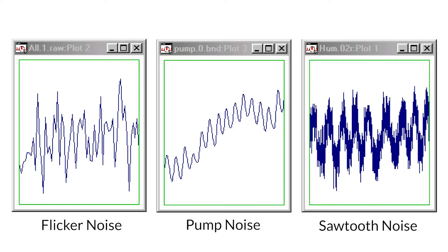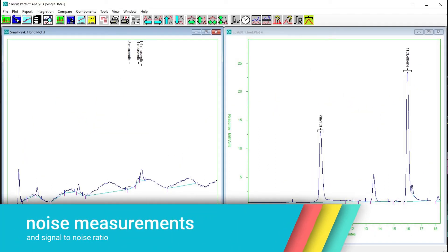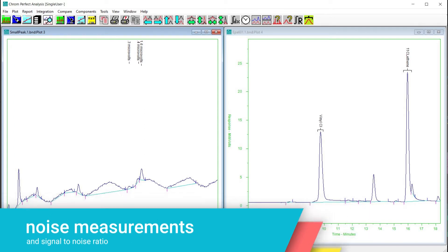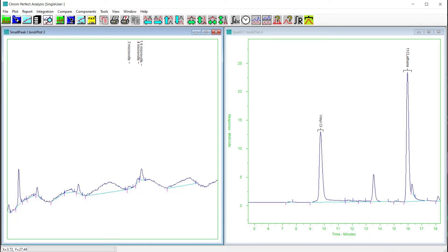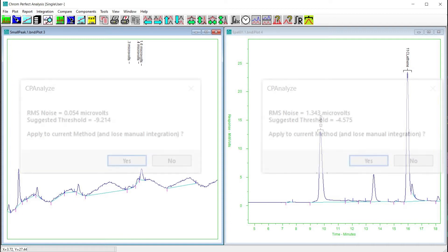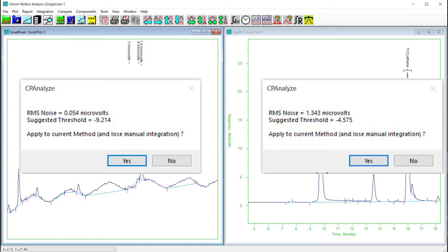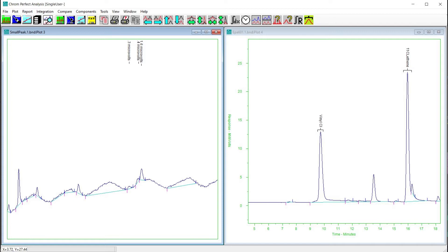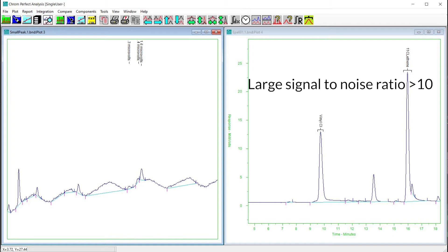Contributors to observed noises are discussed elsewhere. For the purposes of this chapter the source of the noise is not important. Noise measurements and the signal-to-noise ratio. Because noise is a random process, putting meaningful numbers on the amount of noise in a chromatogram is difficult. Experienced analysts can easily make qualitative estimates of noise simply by looking at a chromatogram, but these are usually estimates of the peak-to-peak noise. This measure is not strictly meaningful in a mathematical sense and tends to overestimate the noise because the most extreme noise excursions are taken as representative of the entire chromatogram. A better measure is the root mean square or RMS value, which reflects all of the data in the selected region. Noise is always present to some extent, but it affects results only when its amplitude is significant relative to the peaks of interest. The ratio of a peak's height to the RMS noise is referred to as the signal-to-noise ratio for that peak.